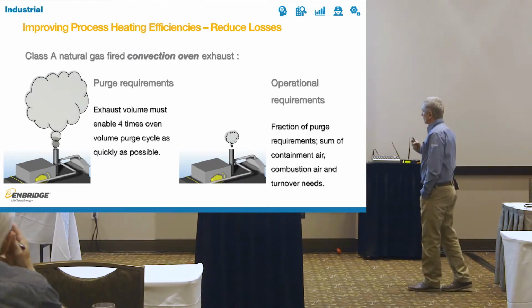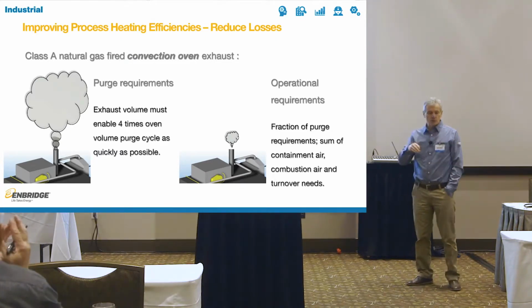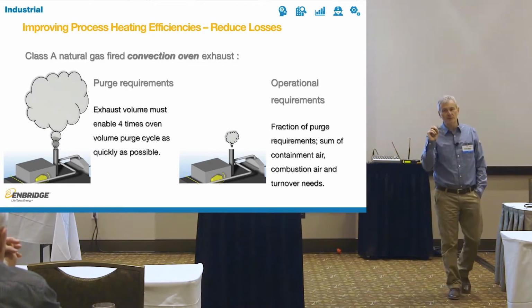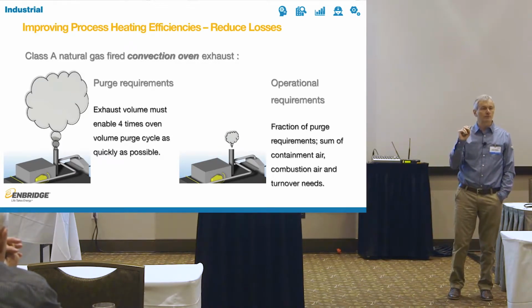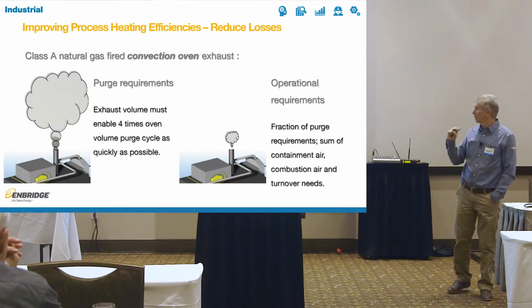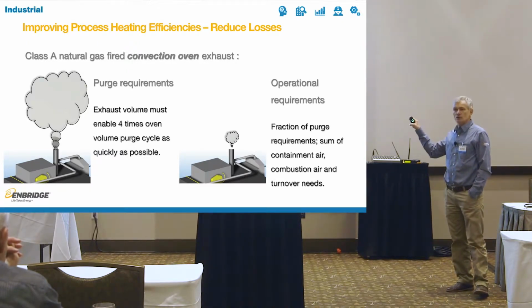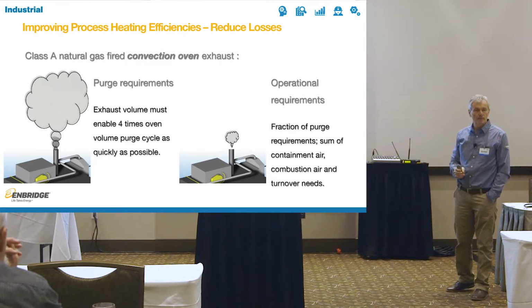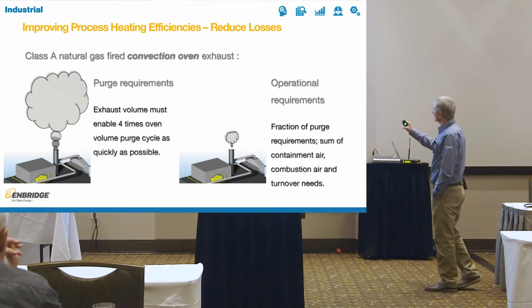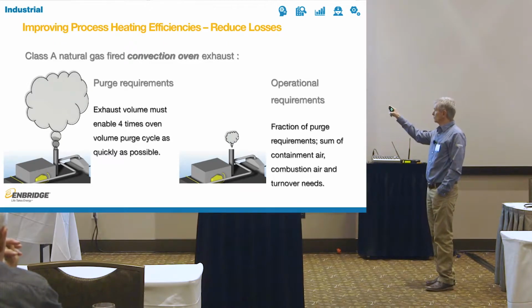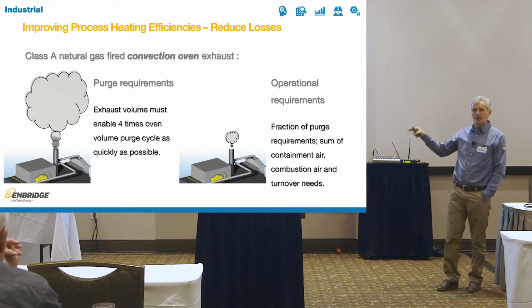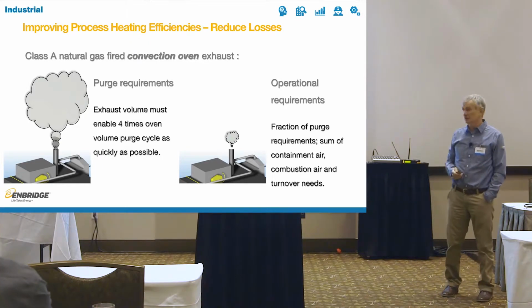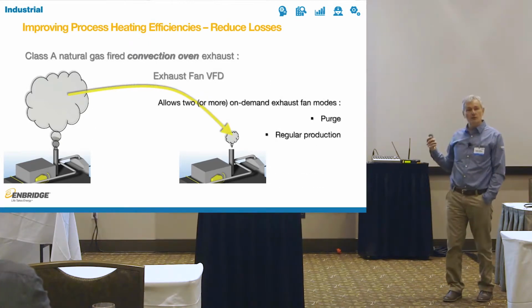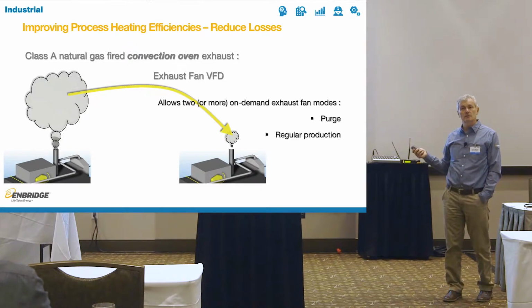But really, operational requirements, and we had workshops on that, we'll have it in the future as well, represent just a fraction of that purge volume. Very small amount. In today's finishing ovens, most of the time you just need to exhaust enough to get rid of the products of combustion. Solvent is only like 9% or something of your loading, very small. To get from purge requirements to operational requirements, today we can do that with VFDs relatively inexpensively. So that's what we recommend doing on most of the finishing ovens.